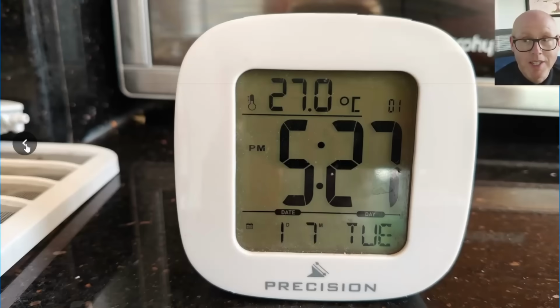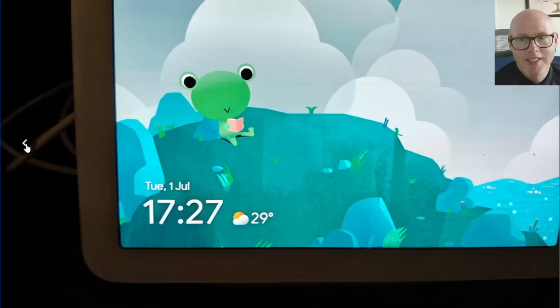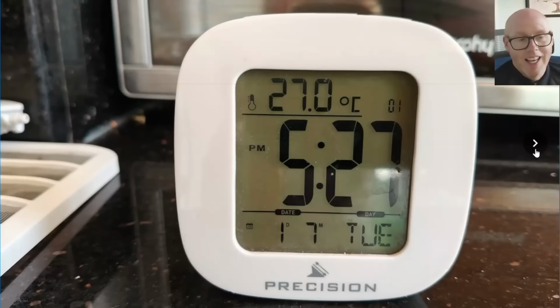However, by 5:27 p.m., it was 27 degrees inside that space, and the external temperature was around 29 degrees. So clearly that AC unit could not keep up with the cooling load necessary.